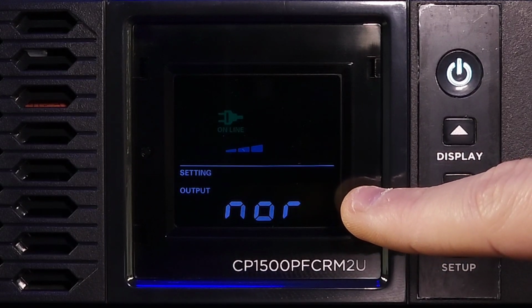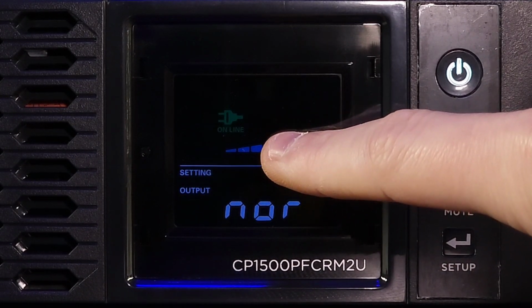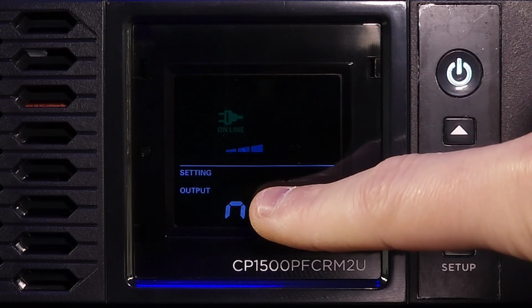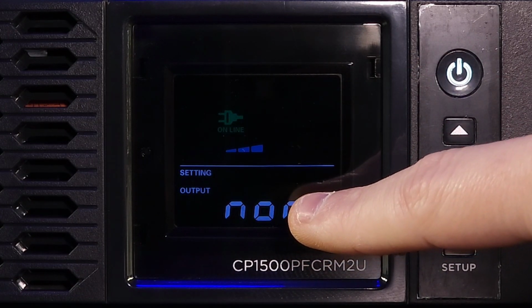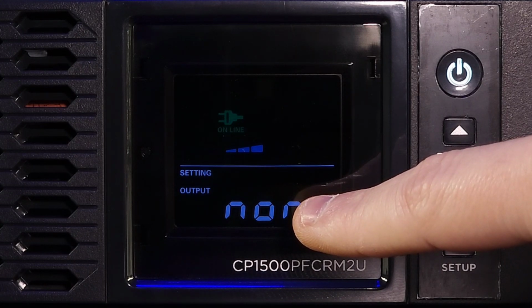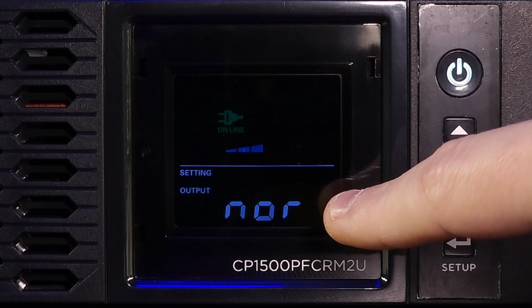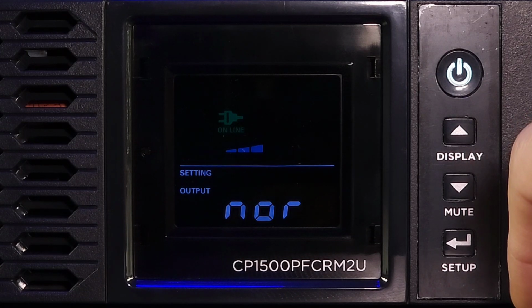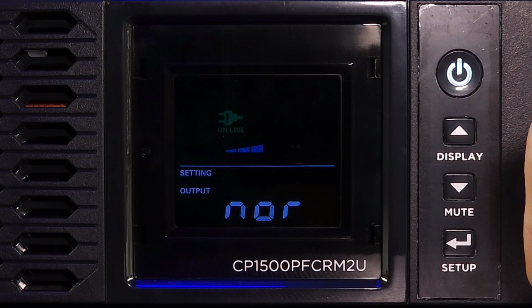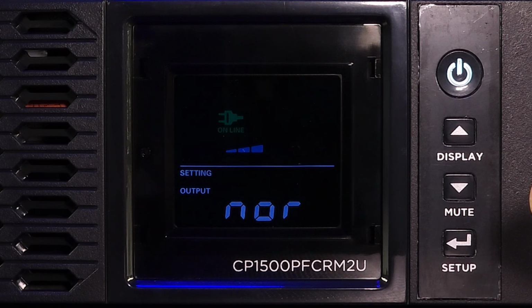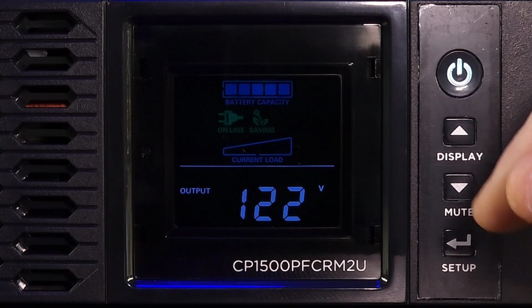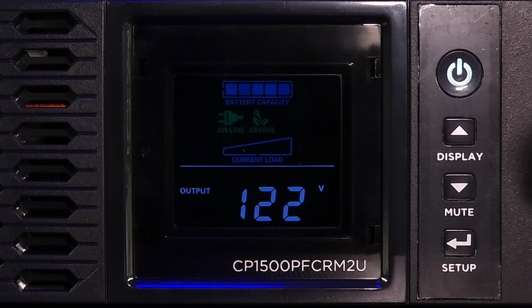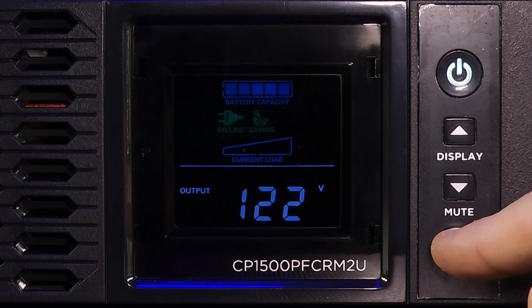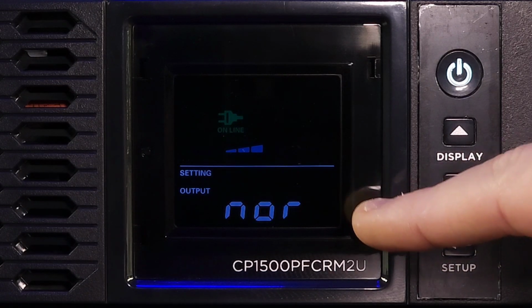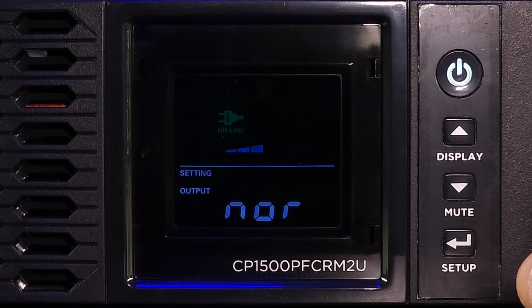Now you're in advanced menu mode, which will also show an icon. Right now our output is set to NOR, normal. You can select the voltage quality of the input utility power. If high is selected, the UPS will go to battery mode more often to supply the cleanest power to your connected devices. If low, the UPS will tolerate more power fluctuations and go to battery mode less often. I'm going to keep mine at normal, but you can change it to low or high.